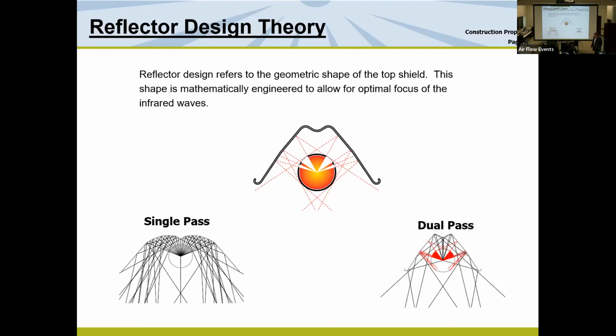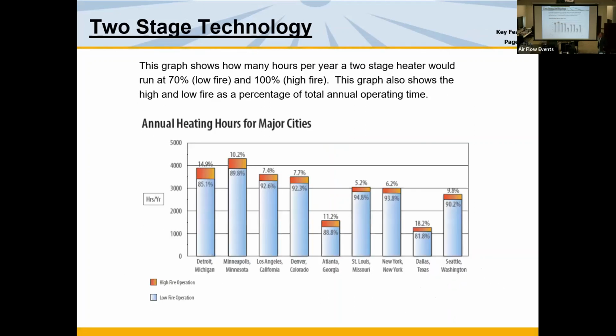We have also made a new heater. I don't know if you've been able to see our video, but our REV series where the reflector geometry is set in the field based upon what people want. And we can give you single pass or dual pass. We can send all the rays down on the first try, or we can bounce them back in the tube depending on what the consumer wants. Next slide. Last thing too, two-stage, we patented two-stage, we created it in 1992.